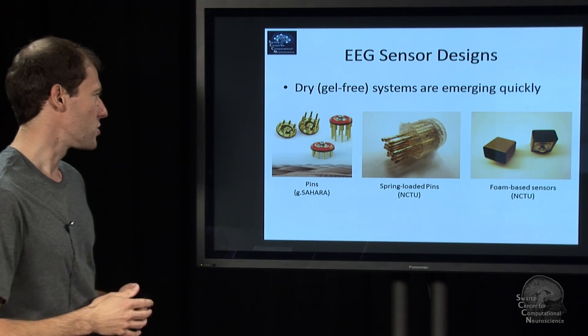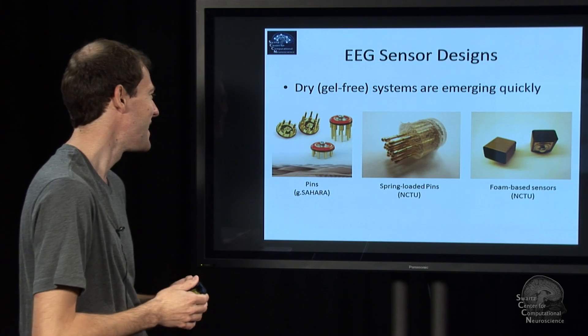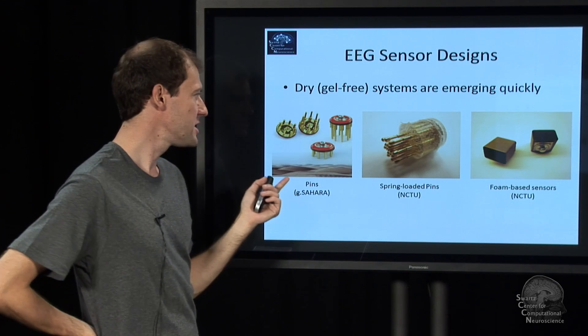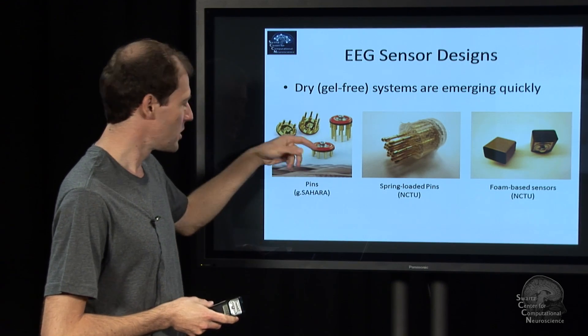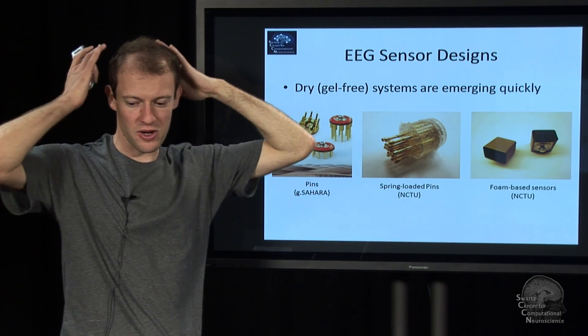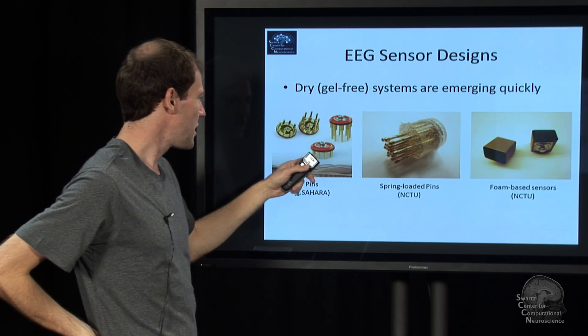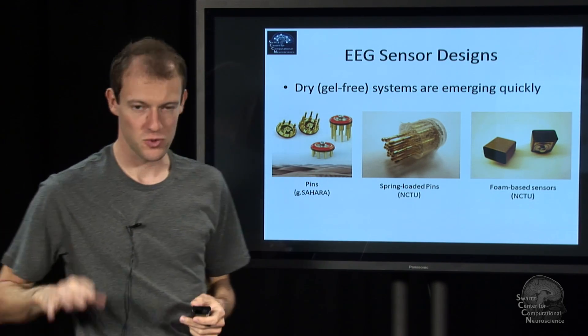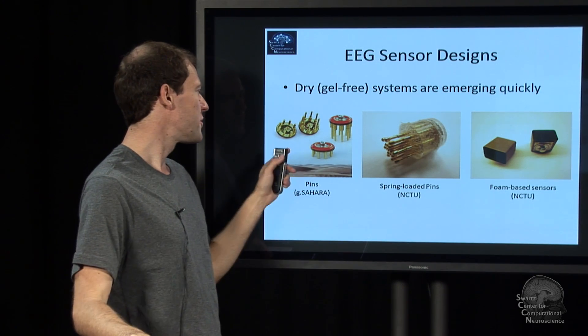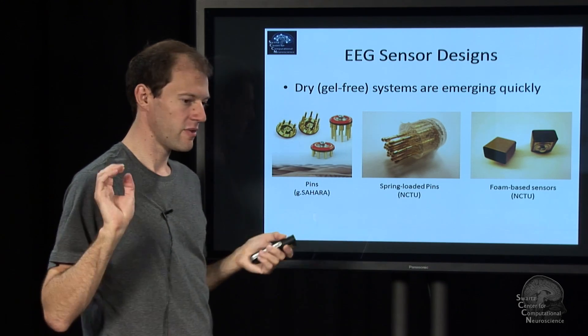There are also so-called dry electrodes. There's a pin-based design — the pins are in the cap and when you put it on, they get through the hair, which is the critical part. They have rounded tips so it doesn't hurt, and they distribute force over multiple pins. Usually it's enough if just one, two, or three of the pins make contact; you don't need all of them.